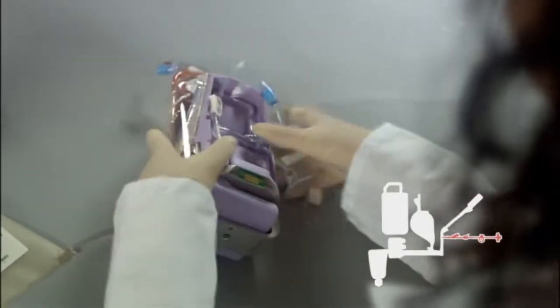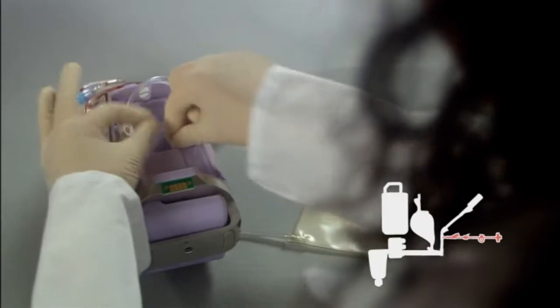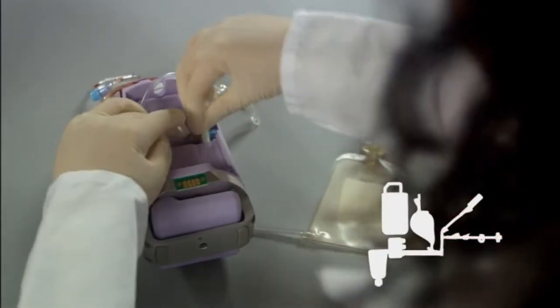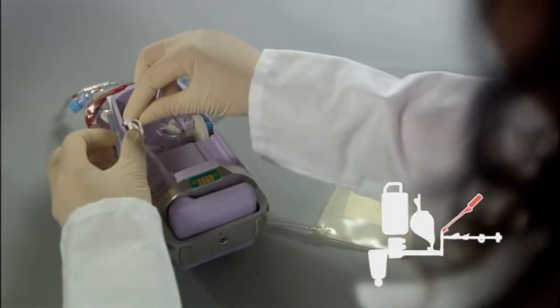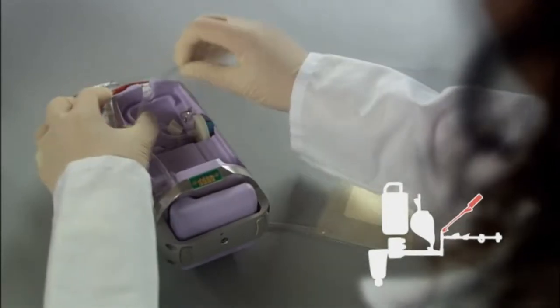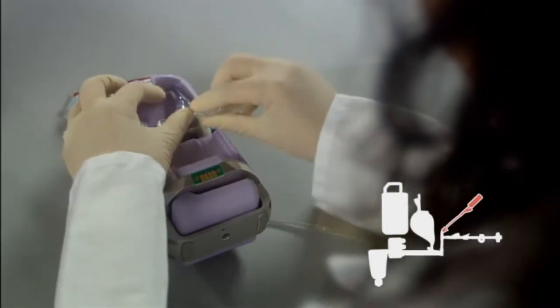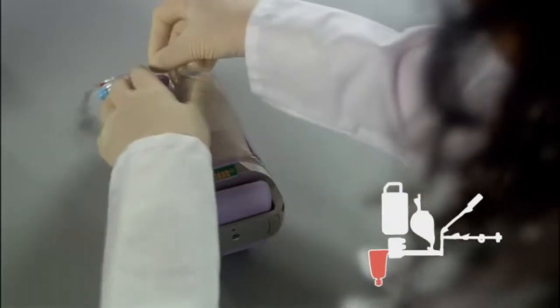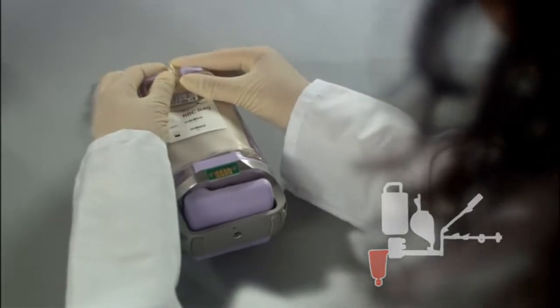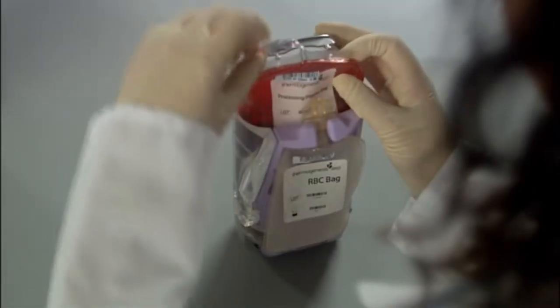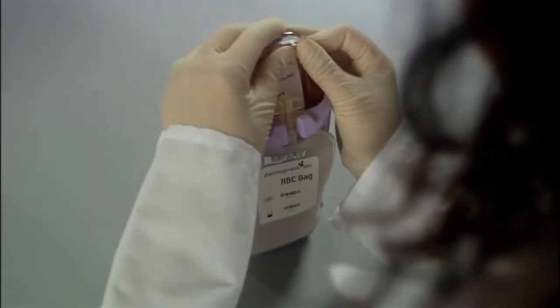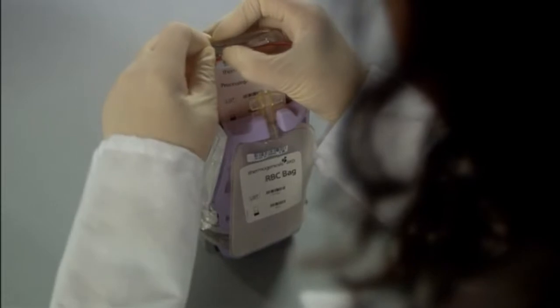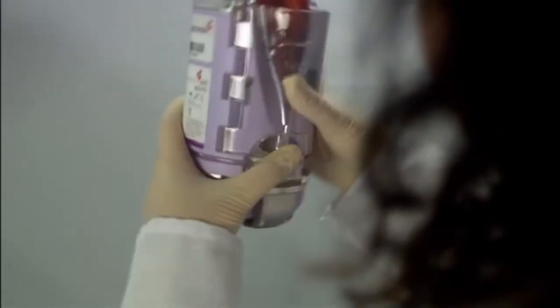Place the DMSO line into the RBC bag cavity, making sure the DMSO filter rests in the groove designed for it. Close the clamp on sampling segment 2 and place it in its specially designed recess. Position the tubing and place the Y fitting over the hook so that the pillow lies over the DMSO filter. Position the RBC bag over the cavity and insert the bag sampling port into the RBC notch. Finally, fold down the pigtail on the processing bag and press the bag onto the bag hanger. Check device closely to ensure that there are no kinks in the tubing and that all tubing is inserted securely into the tubing channels.